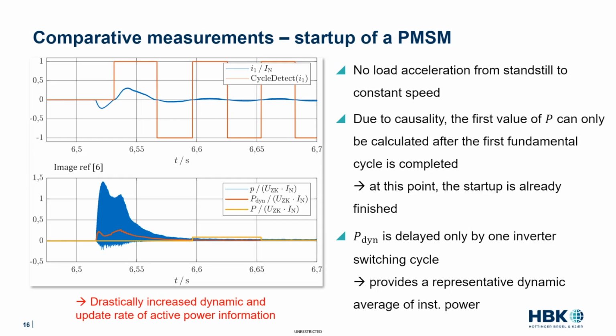And for this, you can see here the red curve, which is the dynamic active power, and it includes the harmonic content. Here you can see the dynamic of the energy transfer per switching cycle of the inverter, and it gives you a drastically increased dynamic update rate and active power information. So this is what you get from that slide.